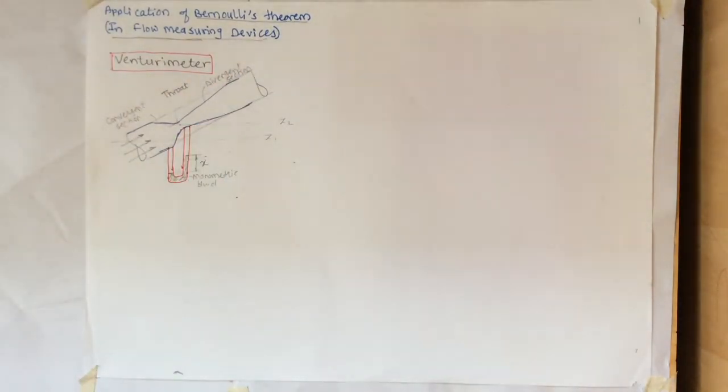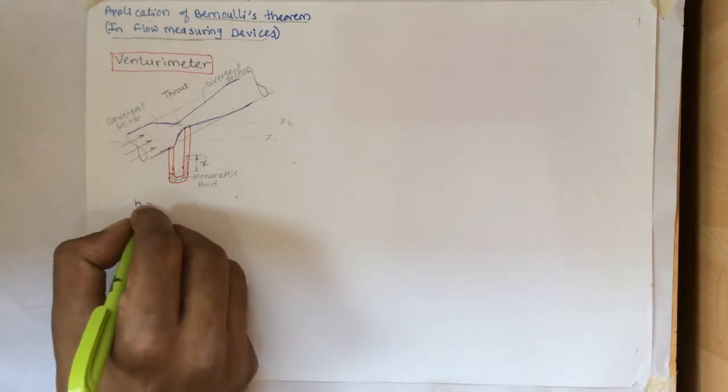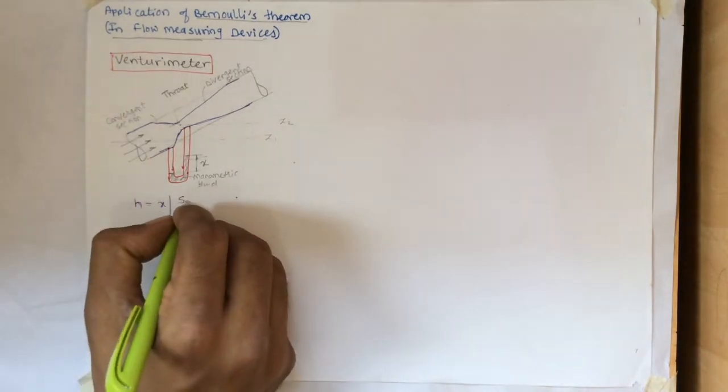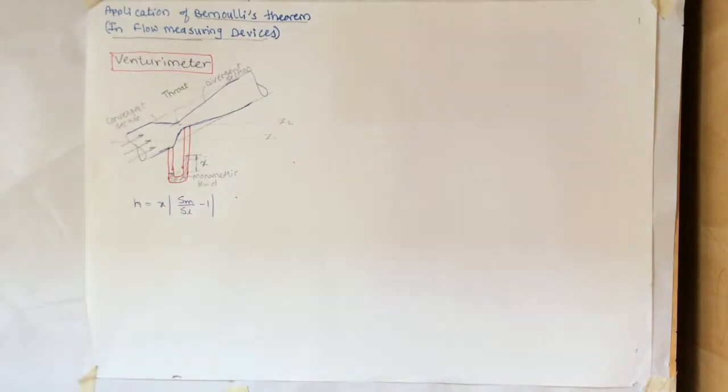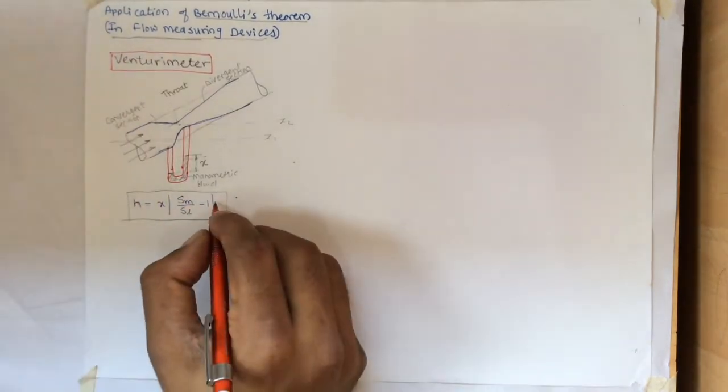As we have used some other fluid to measure the pressure in the manometer, we need to convert this reading X to the equivalent head of the fluid flowing into the Venturi meter. X is the pressure head in terms of manometric fluid, and H will be the pressure head in terms of the fluid flowing through the pipe. So it can be given as H equals X times Sm divided by Sl minus 1.